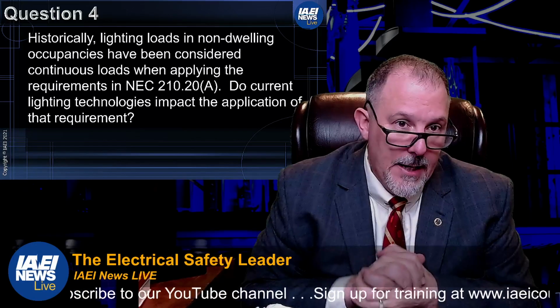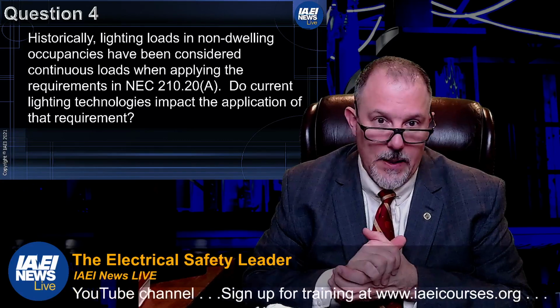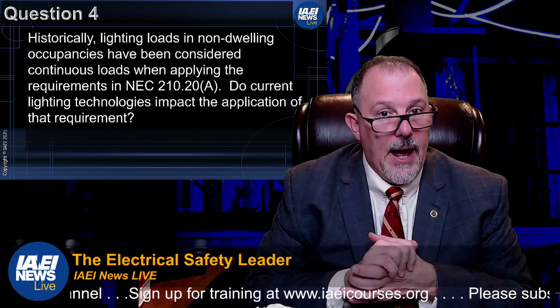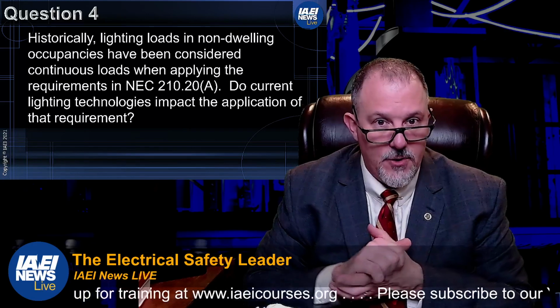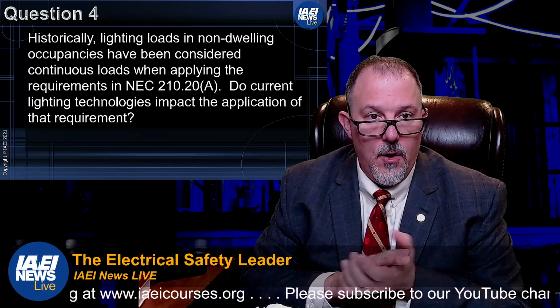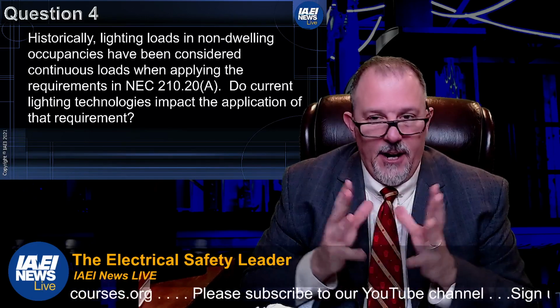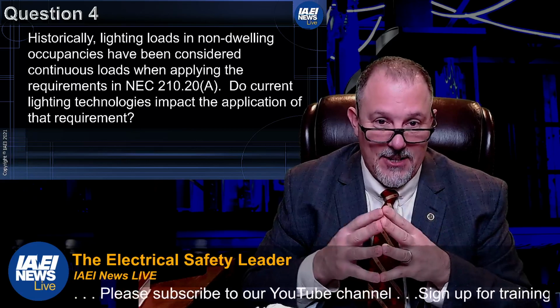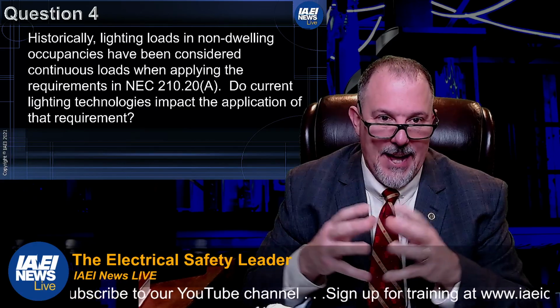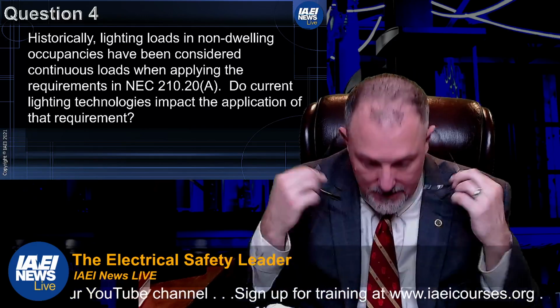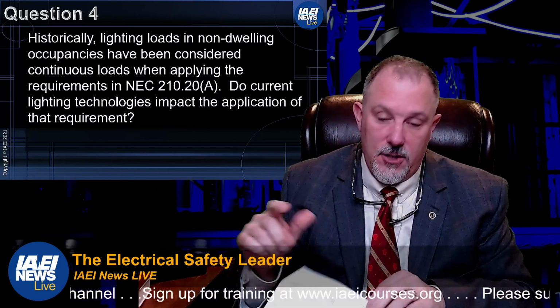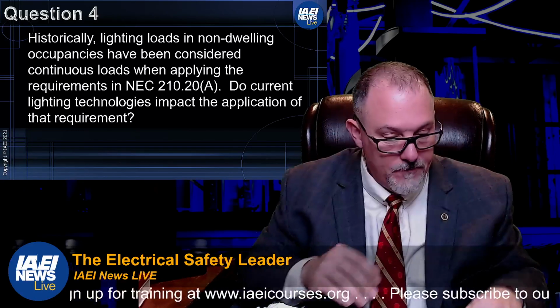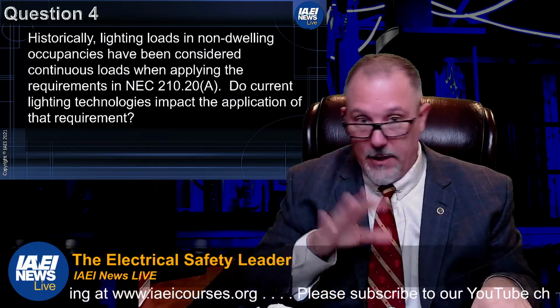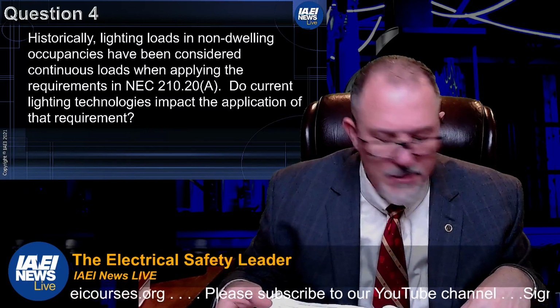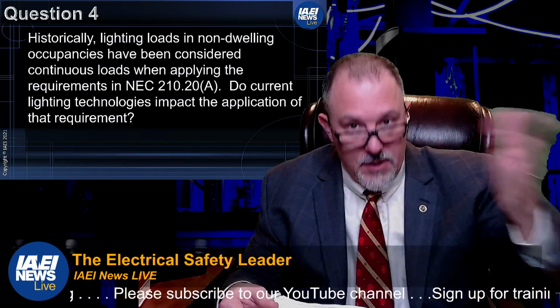Number 4: historically, lighting loads in non-dwelling occupancies have been considered continuous loads when applying the requirements of 210.20(A). Do current lighting technologies impact the application of that requirement? Oh man. So if there was any one change, so let's go to 210.20. Oh, 210.20, not 220.20. Okay, 210. I was thinking 220.12, and I was like, oh boy, because there's another issue there, and we'll get to it. 210.20(A).